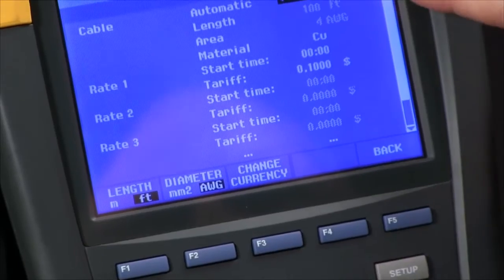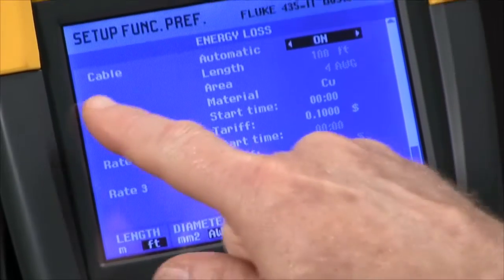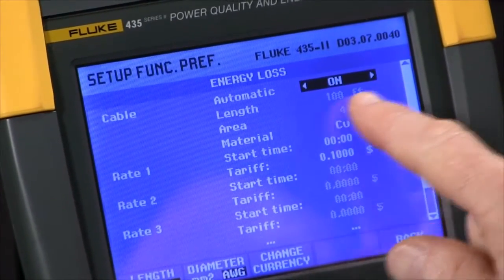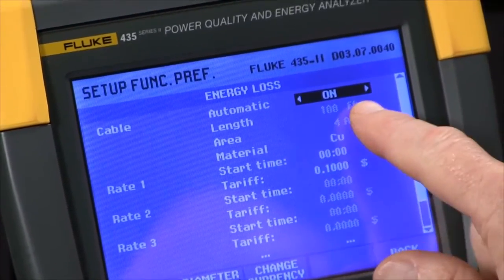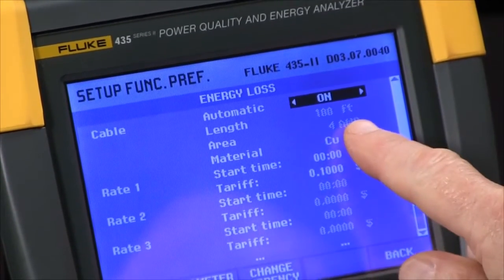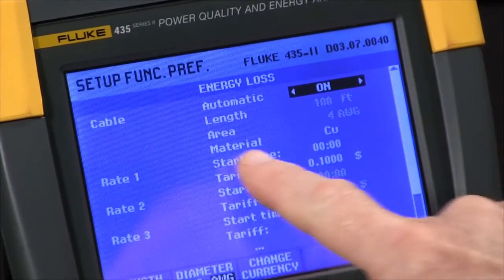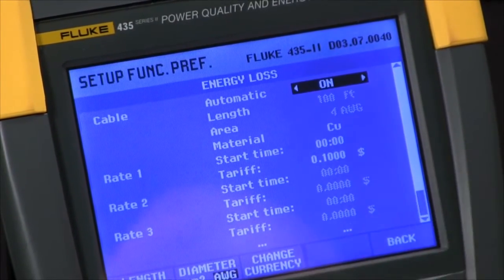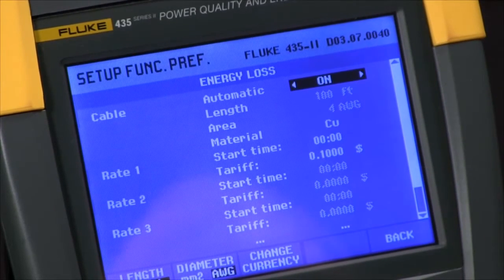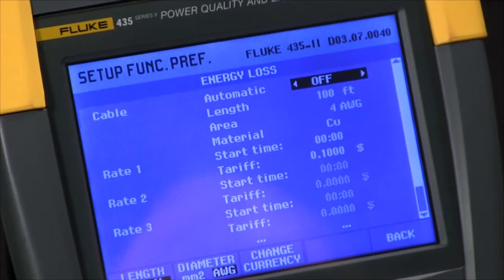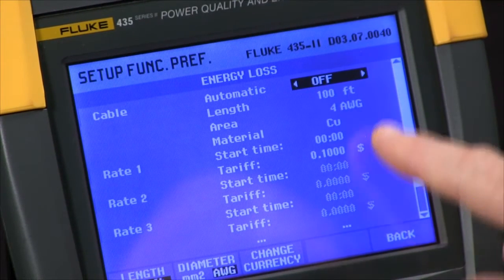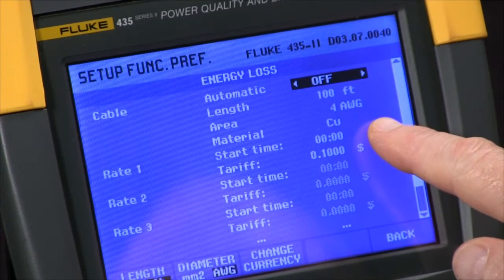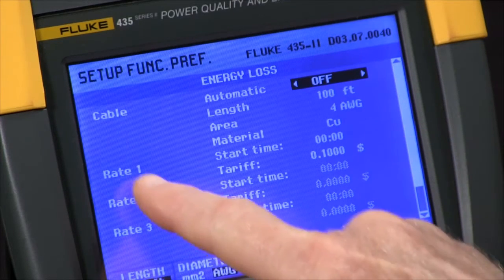At this point, you'll see we have a cable section we configure. If we leave the automatic set to on, we assume a 3% loss and can't make any adjustments. If we toggle that to off, then you can make adjustments to the length and the gauge of the wire.